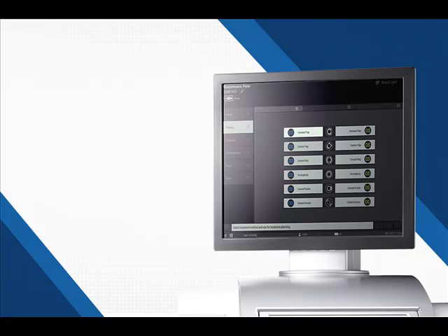For LASIK procedures, and this you don't have to write down, these are approximate numbers. It's just basically to give you a feeling of why the different colors and so on. The LASIK interface is $165. The cataract interface is $300. You cannot use the cheaper interface for cataract procedures, and you cannot use the expensive white interface for LASIK. They are not interchangeable.